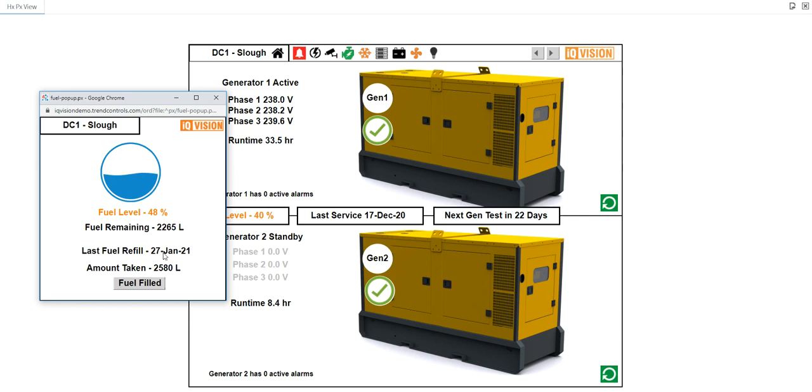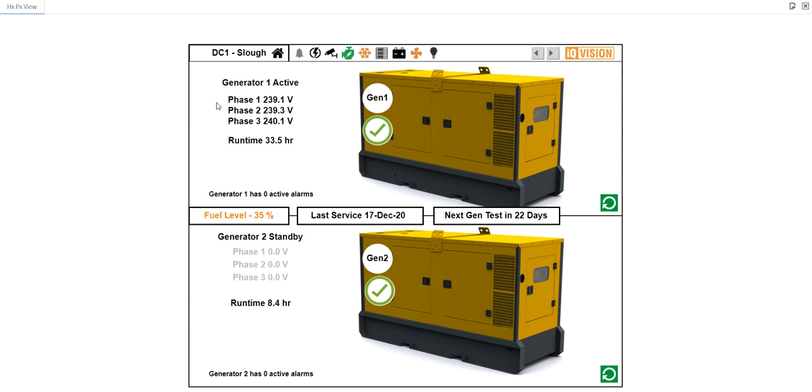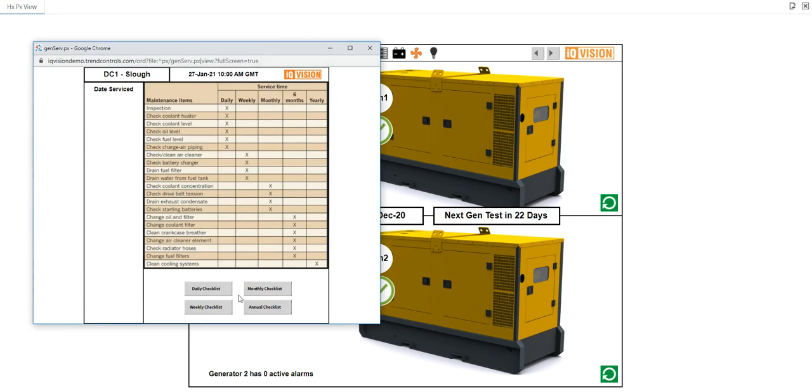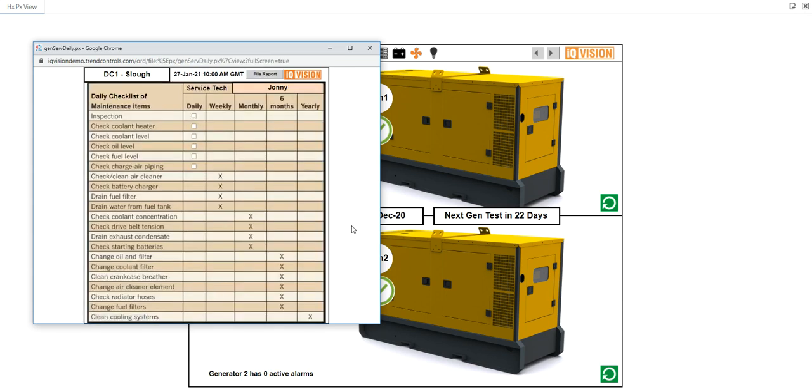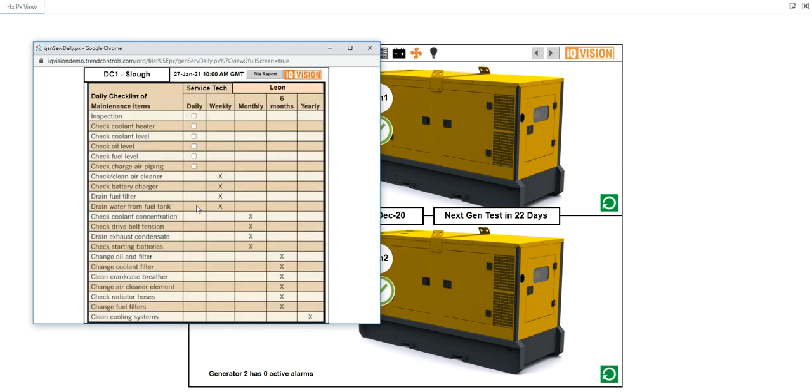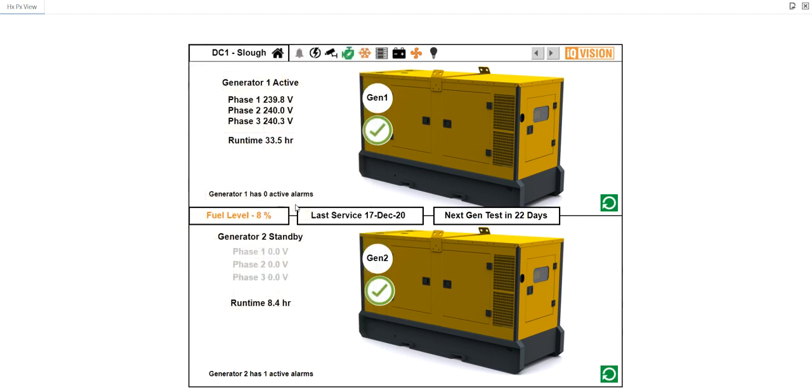There's certain other things we can do on the screen. For example, we can go away and look at the fuel levels. I just happen to have put in a little piece here, which means if we get a tanker in to fill the fuel back up again, I can fill it up. We get a little report saying when the last fuel was refilled and how much fuel it took to fill this up. Any of these little screens can be printed out or indeed included in reports and emailed. There's also something here which is a service record. This particular overview tells me what I need to do, my daily, weekly, monthly tasks. I can just as easily actually get in and perhaps fill in a report saying I've done these tests and then file it. That will commit it to a PDF in the background, which I can then have on record to prove that I am on top of the servicing.